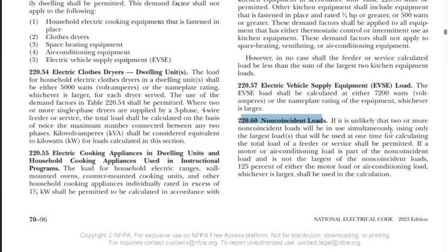As I mentioned yesterday, the first sentence gives us a breakdown of what's going on. Non-coincidental loads are two loads being fed by the same breaker, or OCPD fuse if it's fuses, but both loads are not going to be on at the same time. That's why the first sentence says that.